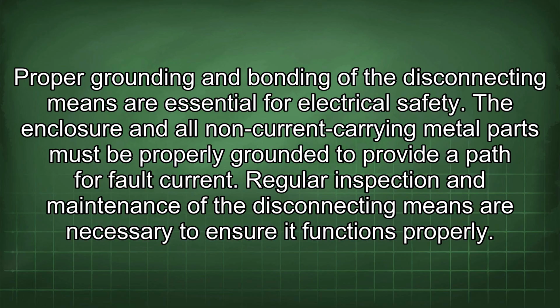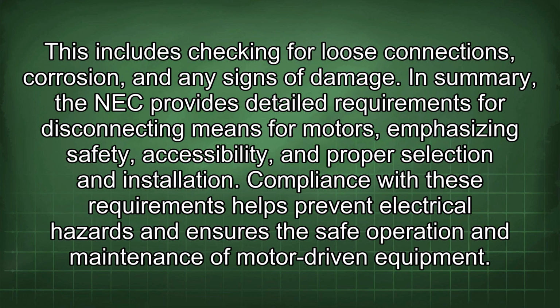Proper grounding and bonding of the disconnecting means are essential for electrical safety. The enclosure and all non-current carrying metal parts must be properly grounded to provide a path for fault current. Regular inspection and maintenance of the disconnecting means are necessary to ensure it functions properly. This includes checking for loose connections, corrosion, and any signs of damage.